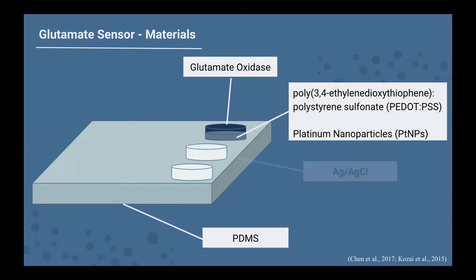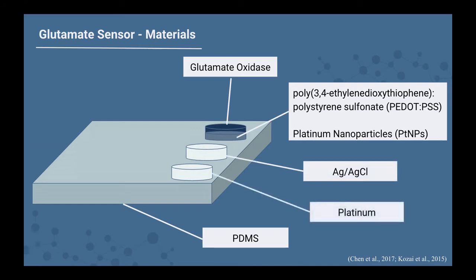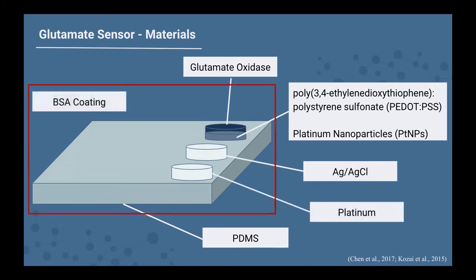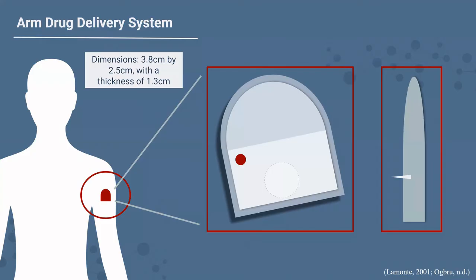The reference electrode is made of silver chloride because these molecules have stable half-cell potentials that do not change over time. The counter electrode is made of platinum because it is an inert material that can carry current. The biosensor is coated with a BSA solution to protect and immobilize the glutamate oxidase.